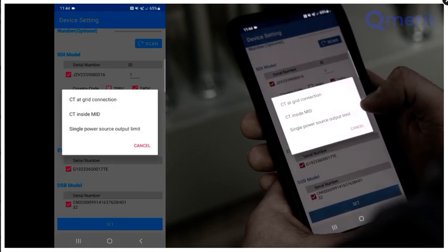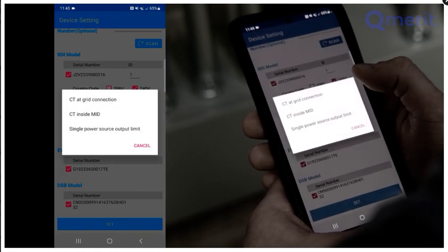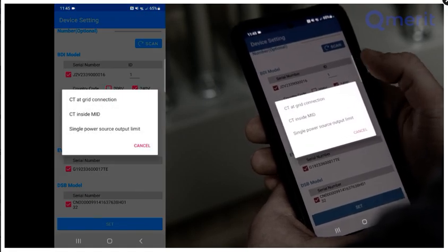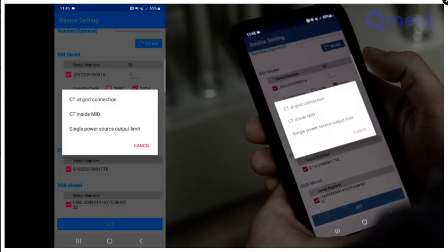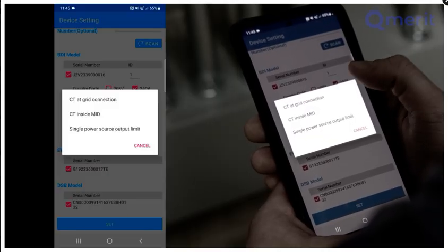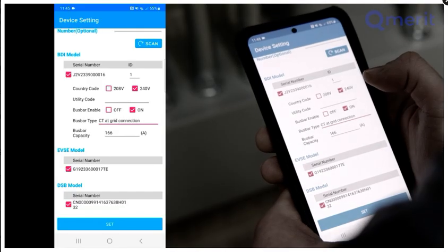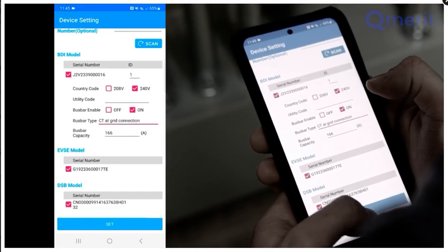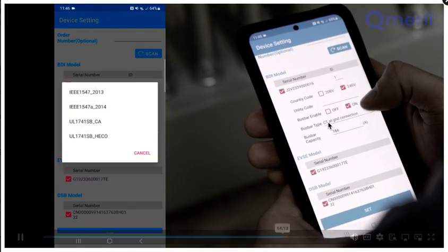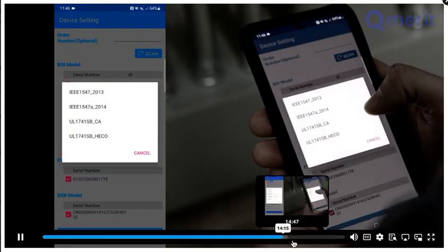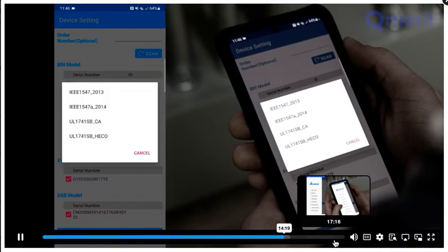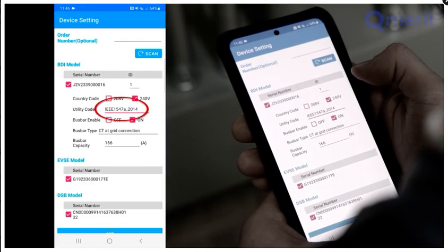Select busbar type. You get 3 options: CT at the grid connection, CT inside the MID, single power source output limit. Because this is a full home backup, we will choose CT at grid connection. Select the utility code. You will get 4 options to select a utility code. Select IEEE 1547A 2014.